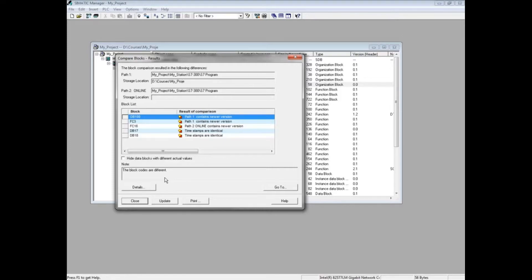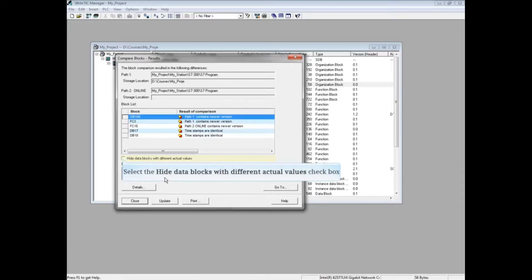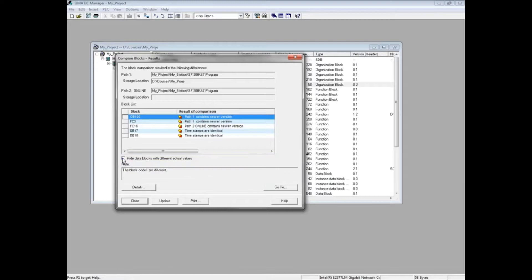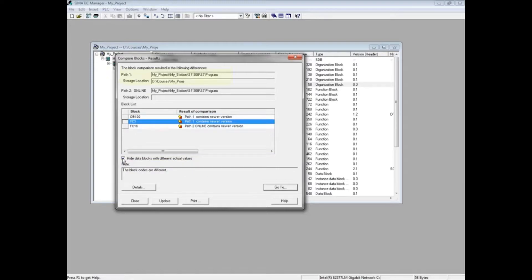SIMATIC Manager then runs a block-by-block comparison. Data blocks will almost always show in the comparison because the actual values are changing. To omit the data blocks, place a check in the box to hide data blocks with different actual values.